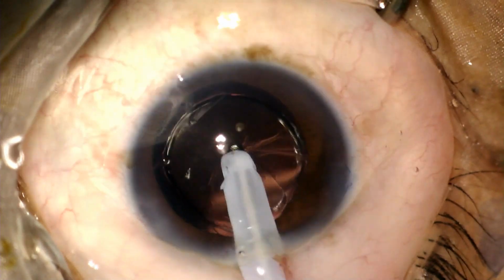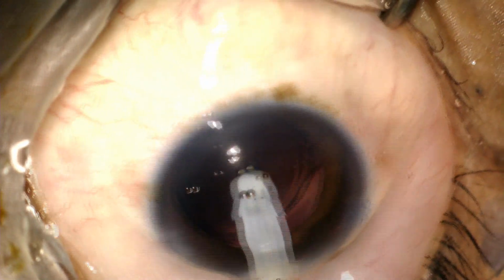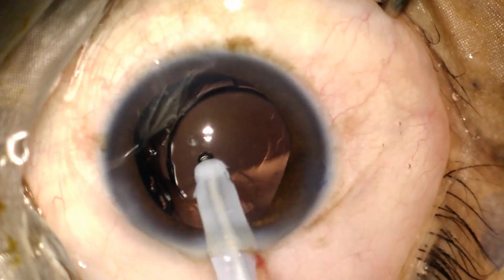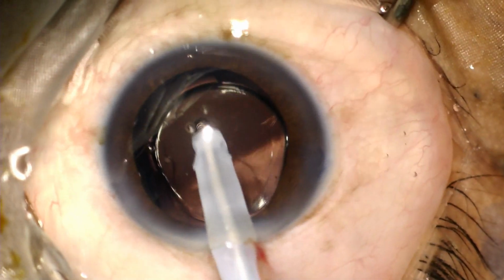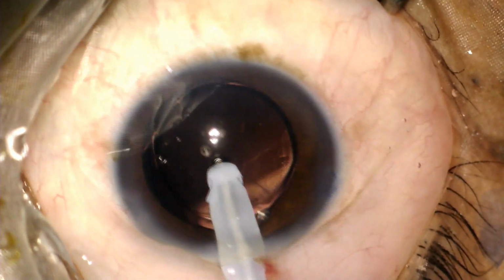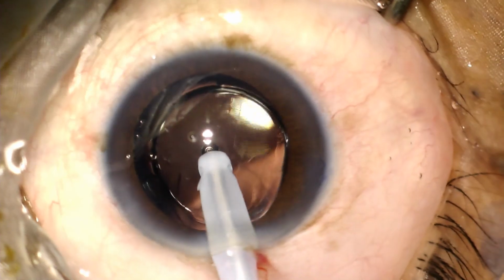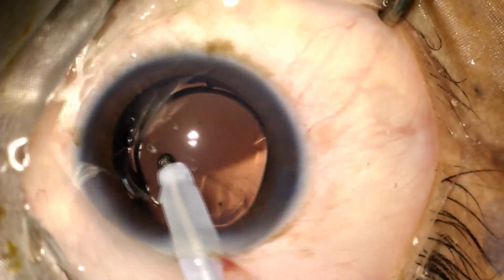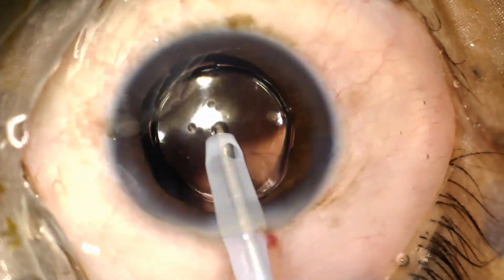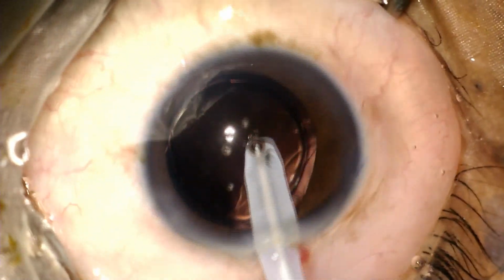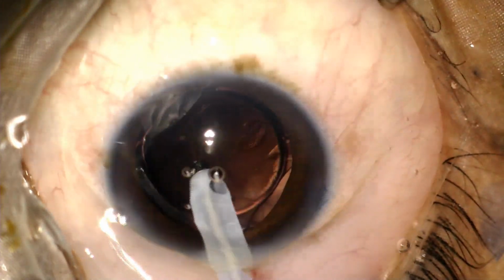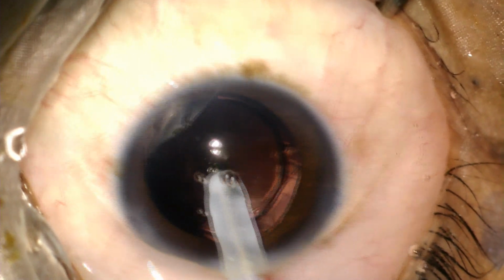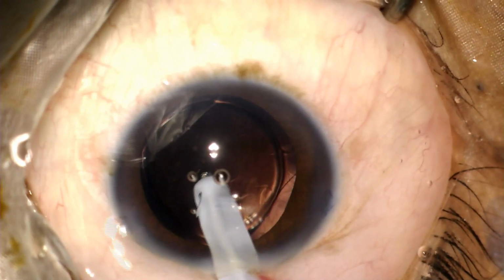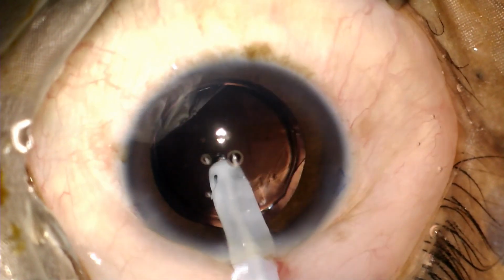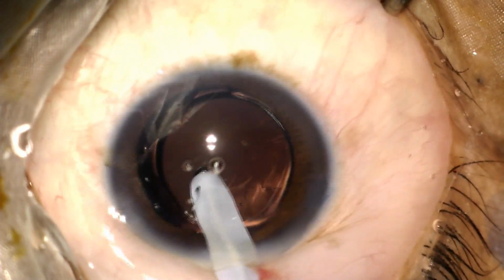Now going to the visco removal mode on my PHACO machine. So here the flow increases. In a Venturi machine you cannot actually control the flow, it's a vacuum based machine. So the bottle height increases to 120, the vacuum is still 500. Can you go behind the IOL to take out the viscoelastic? Yes, you can, and it's important in premium IOLs. But for a beginner surgeon like me, you can get away by just aspirating the visco above the IOL.